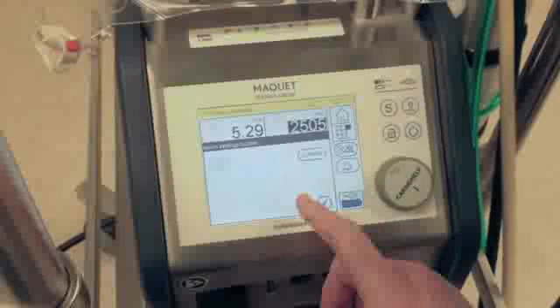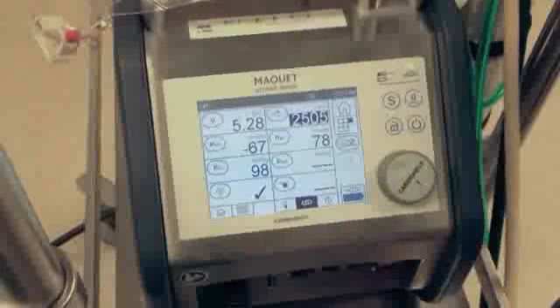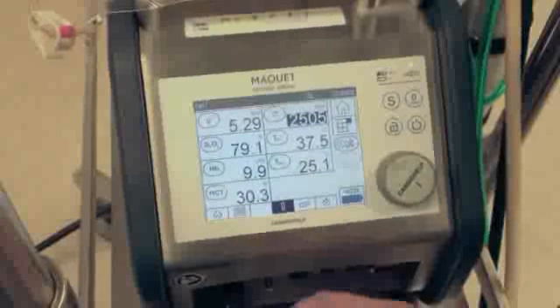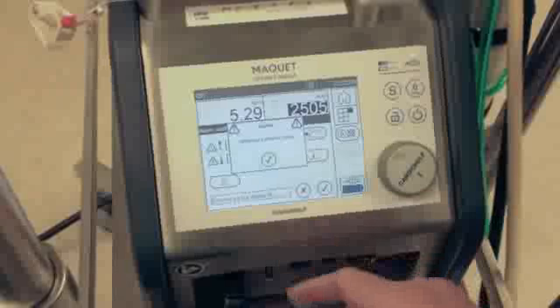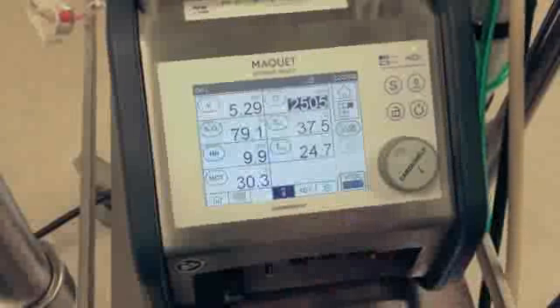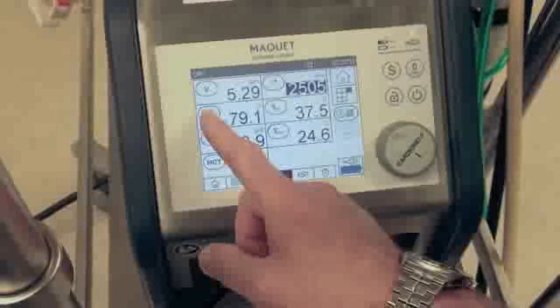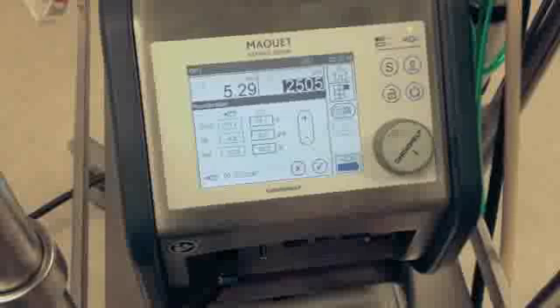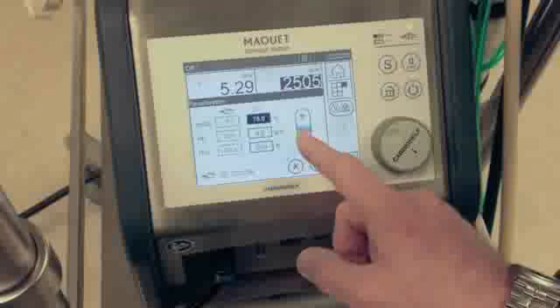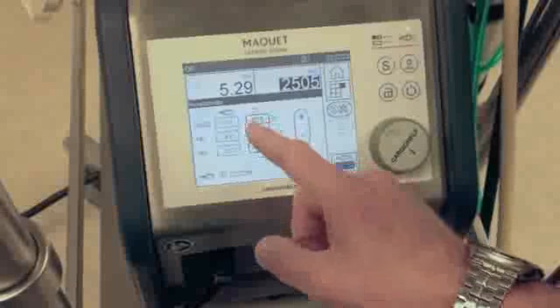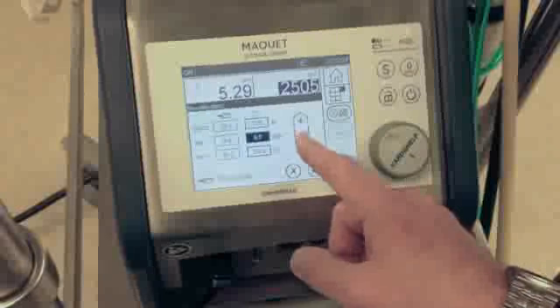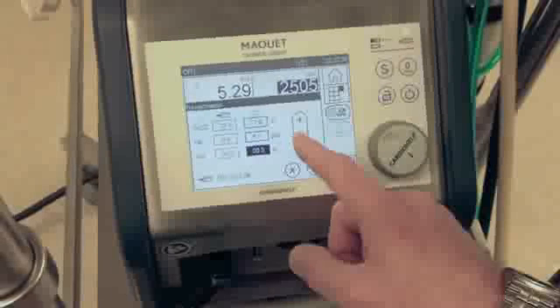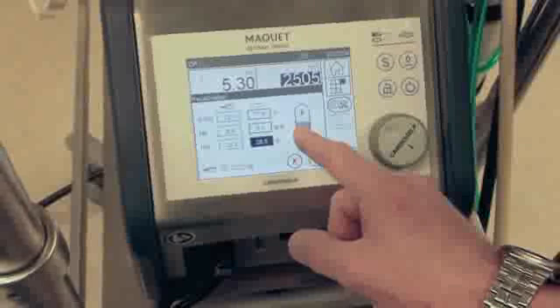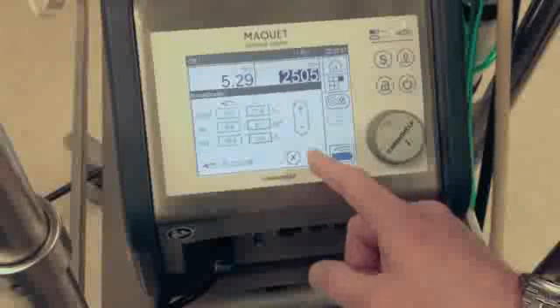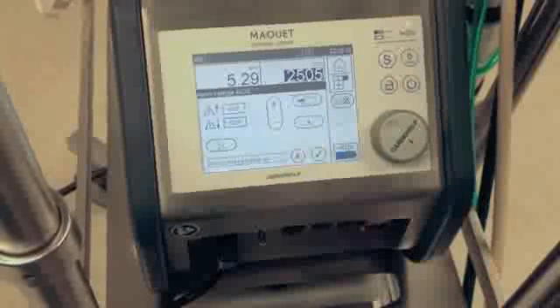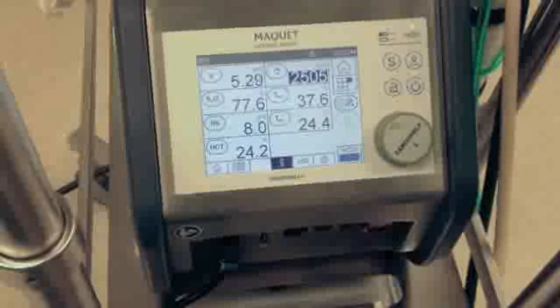You may have some alarms going off, so our perfusionist is demonstrating here how to troubleshoot those alarms. The alarms will be in yellow, so you just hit the yellow buttons and follow the instructions essentially to zero them out. And then the other piece that our perfusionist is demonstrating here is how to recalibrate or calibrate the lab values that CardioHelp will show you with lab values that you draw from the patient from the serum. And you can do that by saving those values first, and then you go in and tap the values you want to change and use the plus and minus arrows to get the values you want. Then hit the green check to verify or confirm, and green check to get out of there, and that's done.